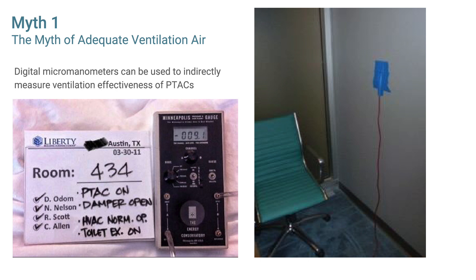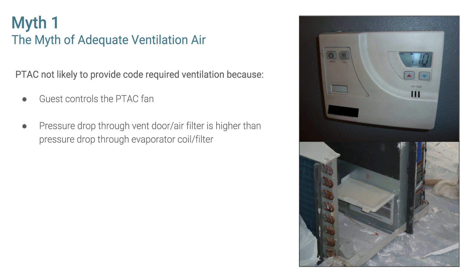In one measurement case with the PTAC damper open, the corridor HVAC system in normal operation, and the toilet exhaust on, we measured negative nine pascals of pressure in the room compared to outdoors. The primary reason the PTAC is unlikely to provide code-required ventilation is that the guest controls the PTAC fan, with no way to limit that unless you prevent the occupant from any control — which is difficult since they can shut the PTAC off or change the fan speed.